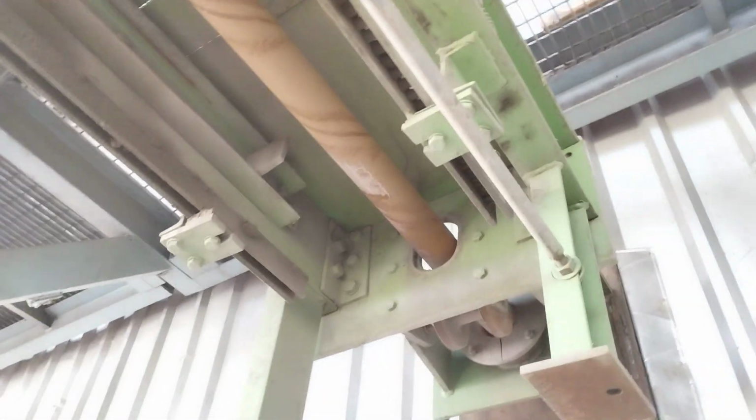When the LRSB is in running condition, this pipe moves from left to right and rotates clockwise, then on return it rotates anti-clockwise. This zone is the final superheater outlet zone. That's why the ash is stored on the pipe plate or other side. To clean this ash, we need the soot blowing system.